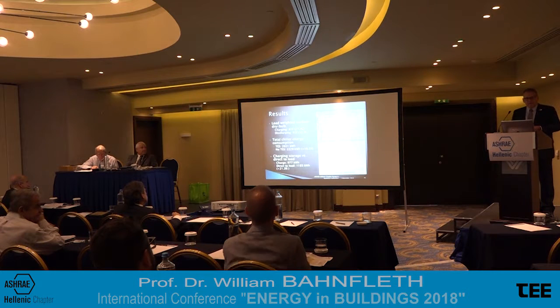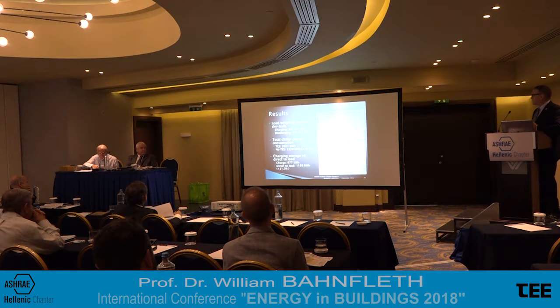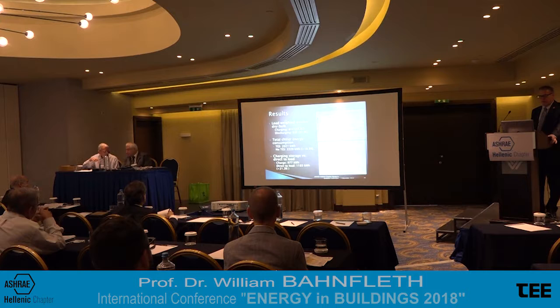And so the result is that with a load weighted outdoor dry bulb of 27 degrees when we're charging and 33 when we're discharging, that's a pretty big shift in temperature that will help us save energy. So the total chiller energy consumption with thermal storage is about 2,000 kilowatt hours, and without storage it's about 2,200. So there's a difference of 10% overall, which is fairly significant.